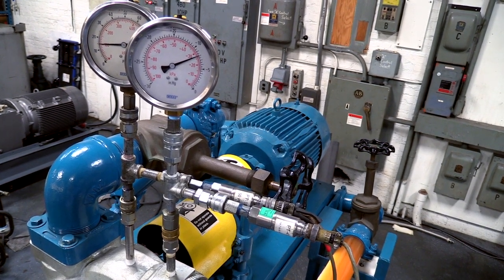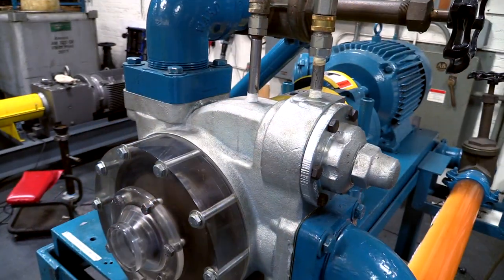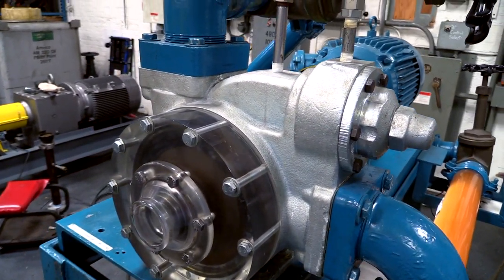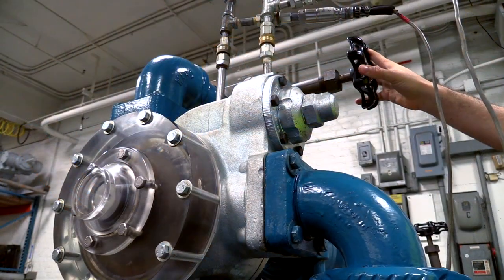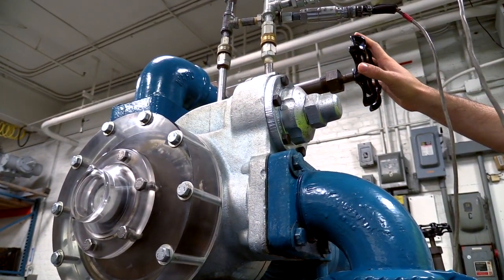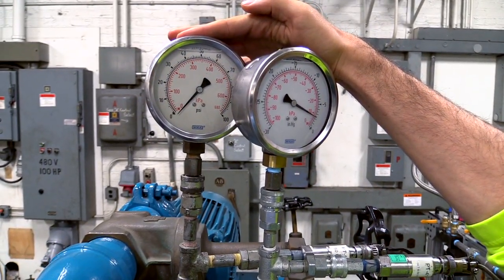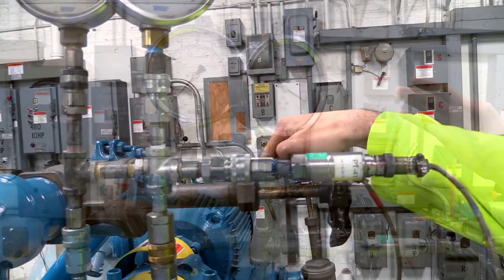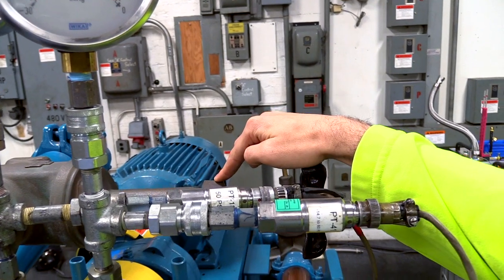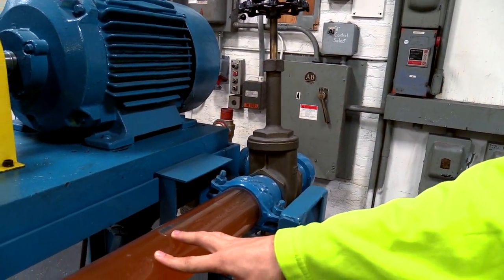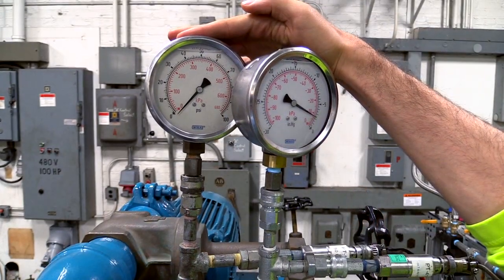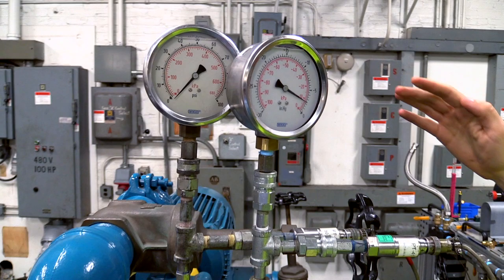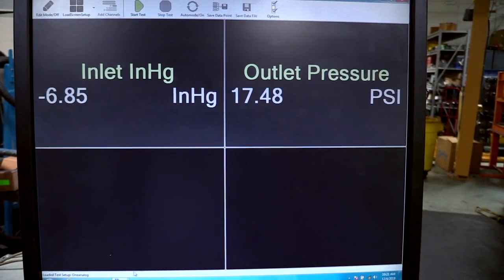This test lab will allow us to measure conditions and performance and show us how to mitigate cavitation destruction. The test stand has clear inlet pipe runs leading to the pump. All conditions are being carefully controlled and monitored so that we can fairly evaluate multiple pumps under identical settings. These gauges and valves control the operating conditions, and we can see the inlet and discharge pressure on this monitor.